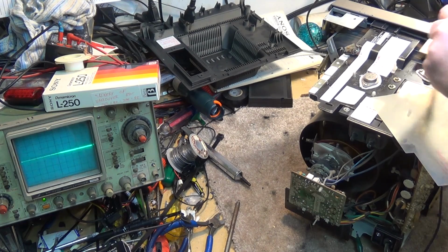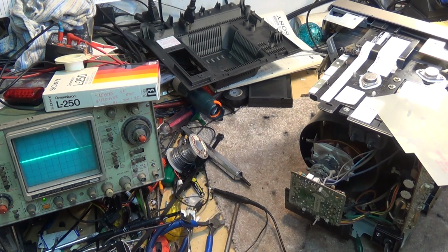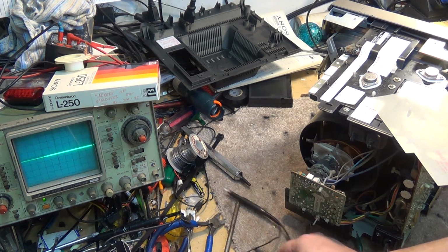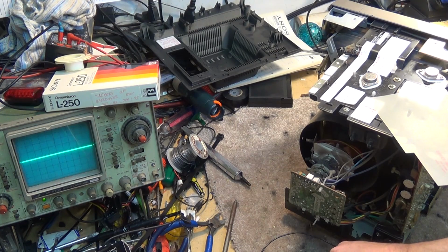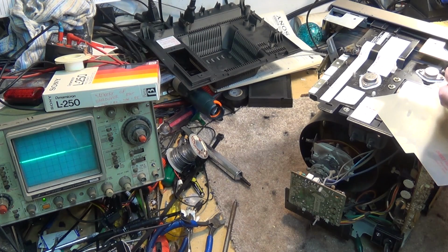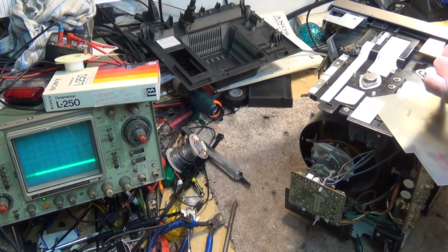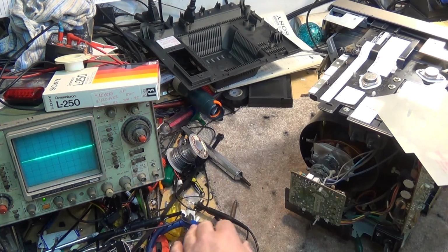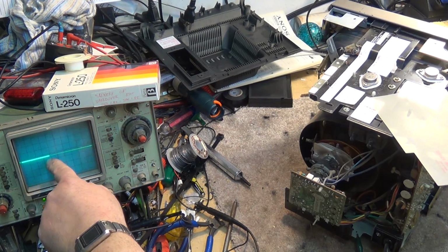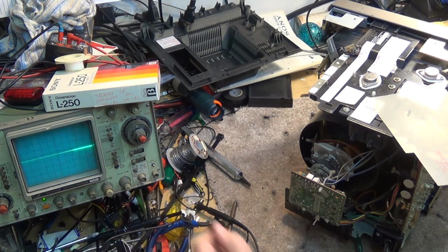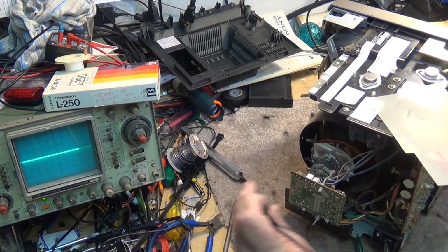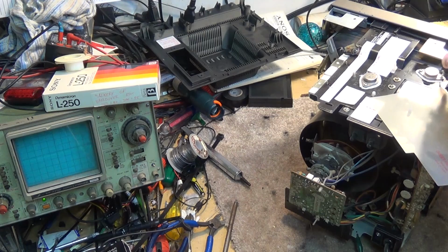No, that's just the DC voltage, so our oscillator's not running. I could put my meter on there and check it since there's no 1000 volt pulse. There was a little bit there when I first turned it on, it tried to start. I saw some oscillation, and then it shut off.